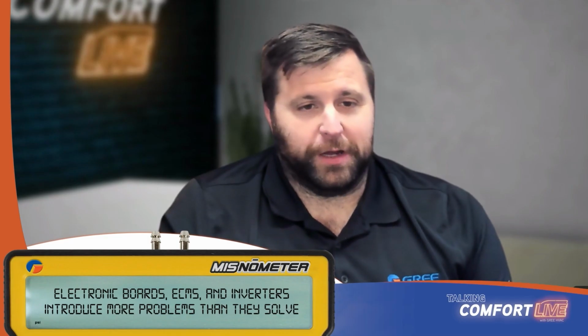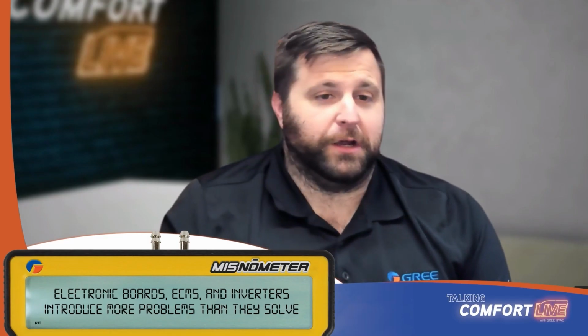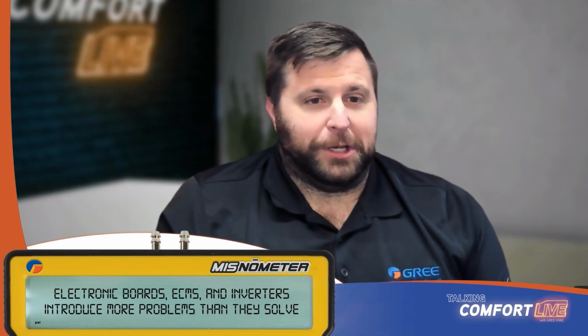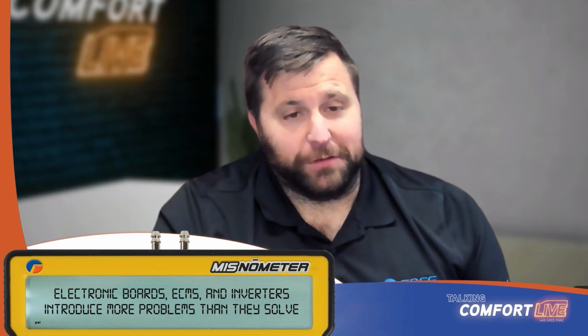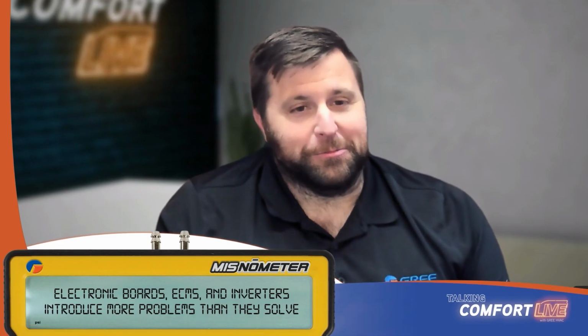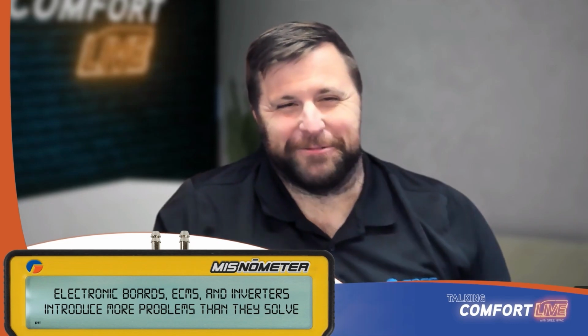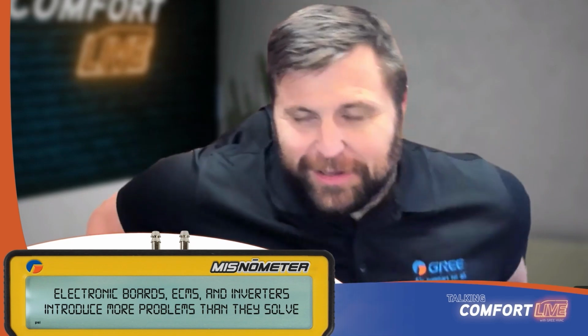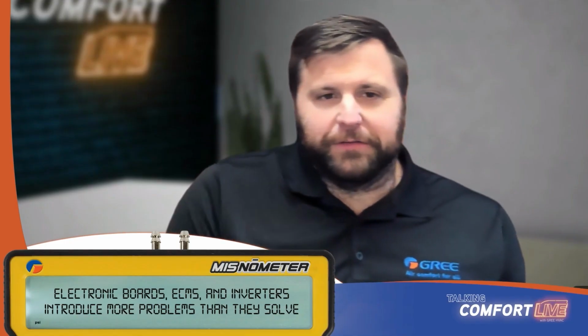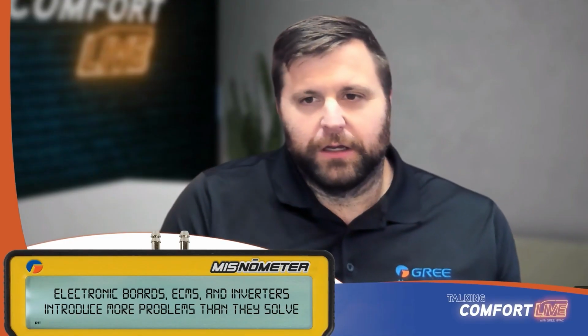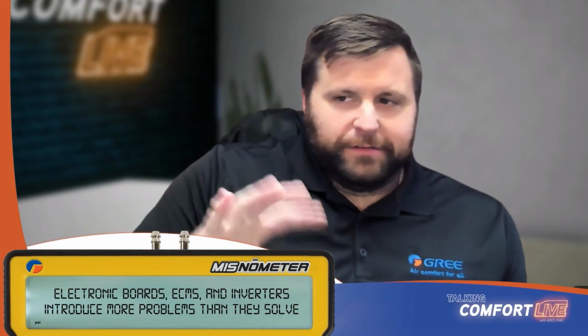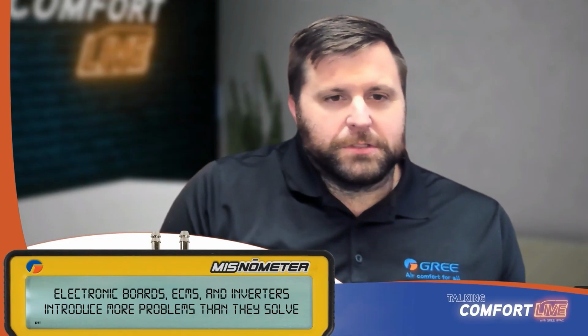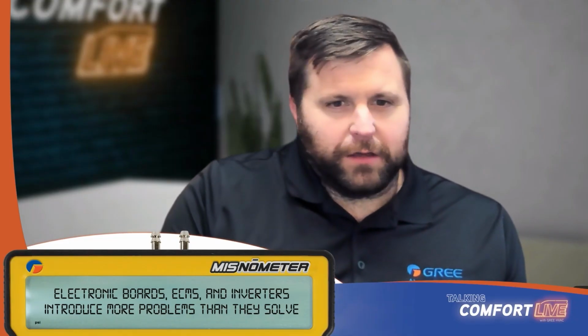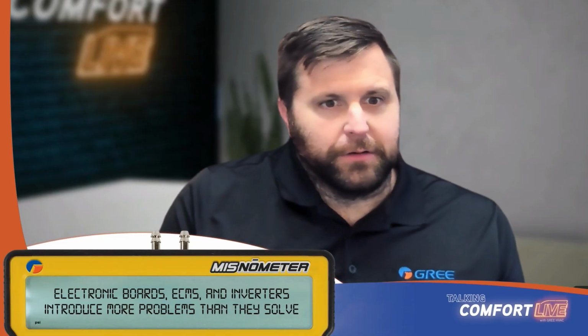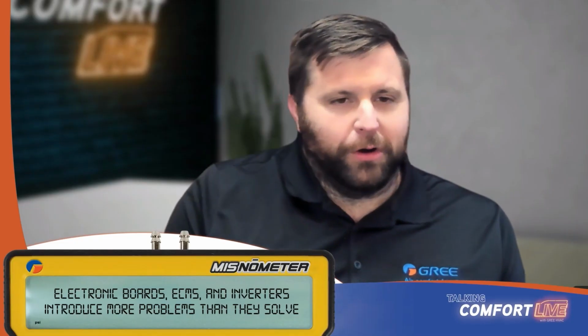If you've got one of those capacitors out, your voltage isn't high enough, it may not run. Right. Well, of course, what you can see sometimes is maybe the voltage isn't very high, but it runs anyway. There's a couple different things like that we see from time to time. And then you can check the diodes. Doing a diode check, that's actually what turns the motor. So it's just an additional check. In that case, it's like checking the contactor. That's what brings the motor on, right?